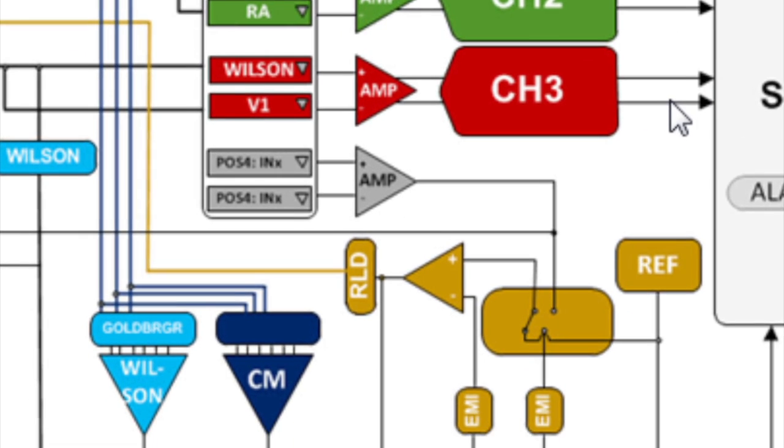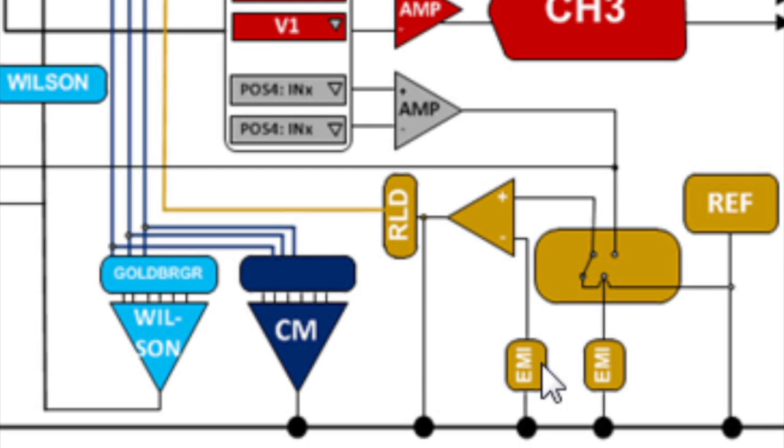To the bottom of the block diagram, we have ECG features such as a right leg driver to create a common mode level for the patient. And to the left we have a common mode block as well as a Goldberger and a Wilson terminal block for the 5-lead and 12-lead ECG applications.